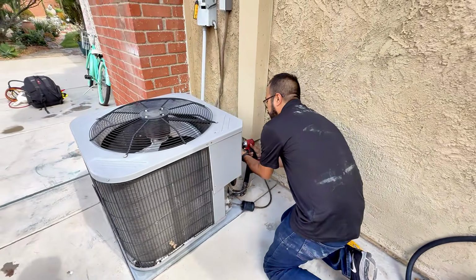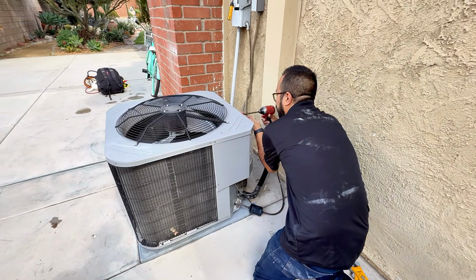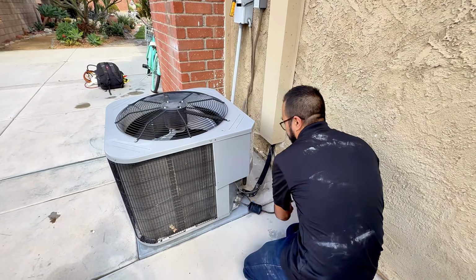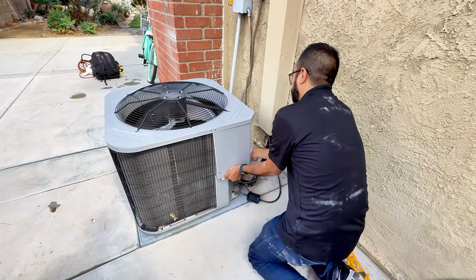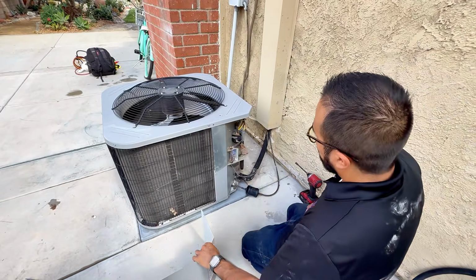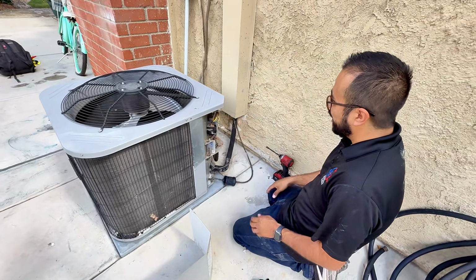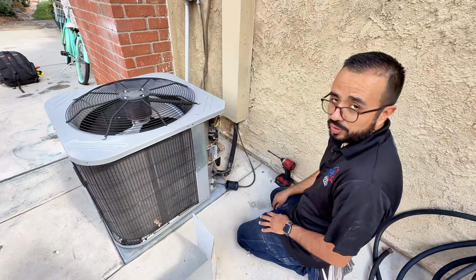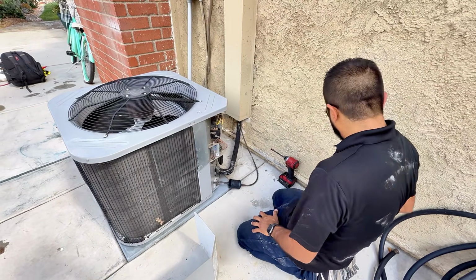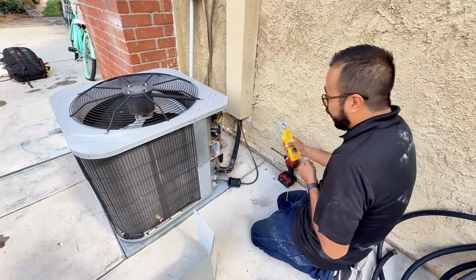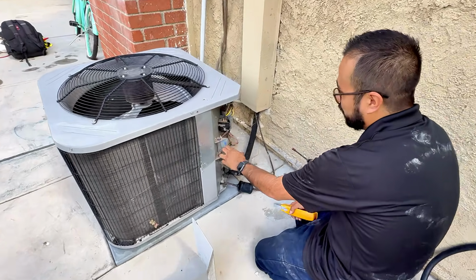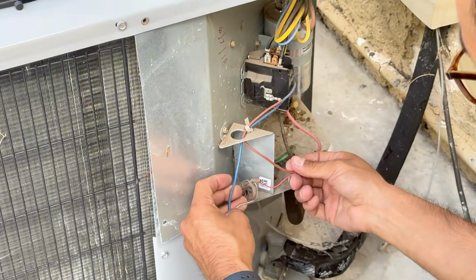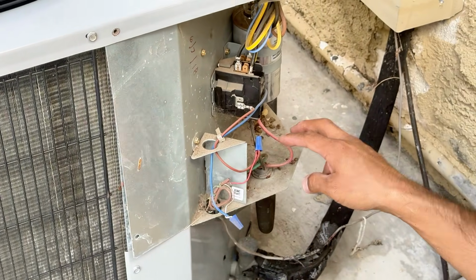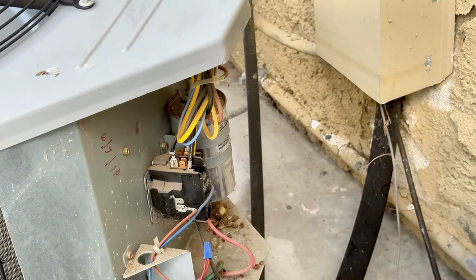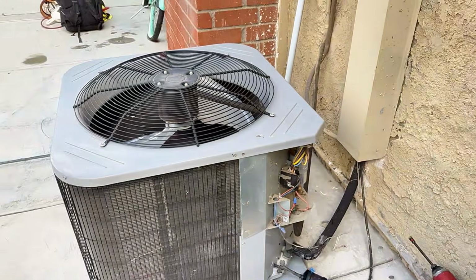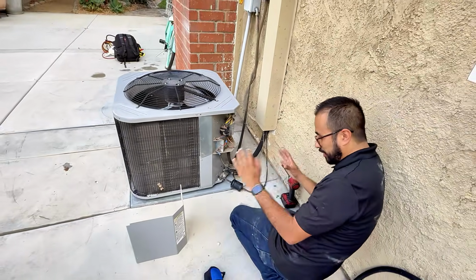So what I'm going to do here is go ahead and open the panel up. All right, so this is pretty simple, as easy as it can get when it comes to a unit. Very, very simple because you just got your two wires. You don't even have pressure switches, look at that, it's just got two wires coming in here. You got your high voltage going to your capacitor, condenser fan, and compressor. That's it, this is as simple as I can get.